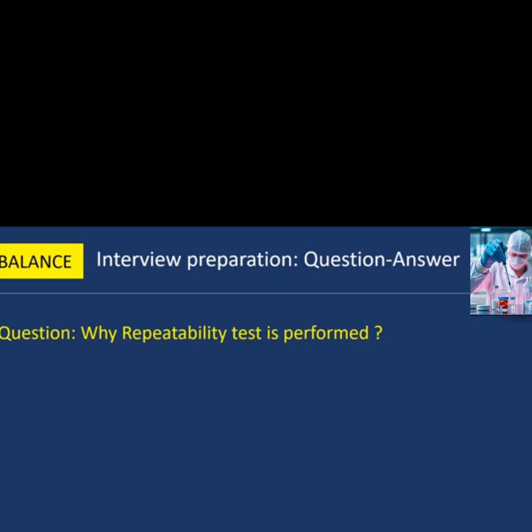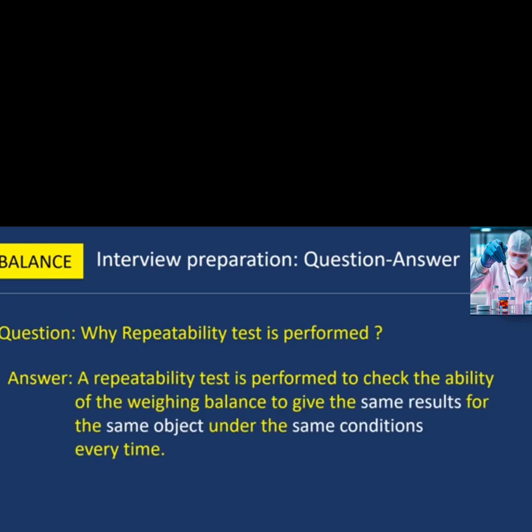Next question: why is the repeatability test performed? A repeatability test is performed to check the ability of the weighing balance to give the same results for the same object under the same conditions every time.